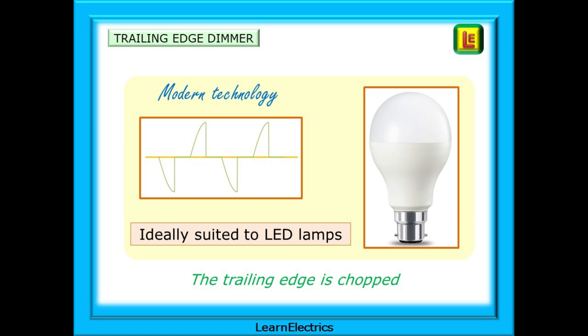Trailing-edge dimmers work by cutting off the trailing edge of each half cycle. Starting from zero volts, the voltage steadily increases, and this makes them ideal for LED lamps. The technology to make LED lamps dimmable relies on some of the components being built into the dimmer switch, and the rest of the components being built into the base of the LED lamp, which is why we must have a correct pairing of dimmable LED lamps and LED dimmer switches to make them work properly together.